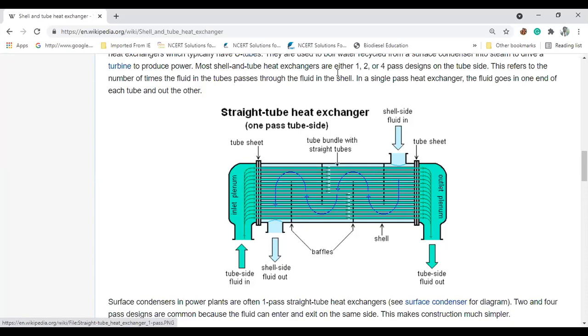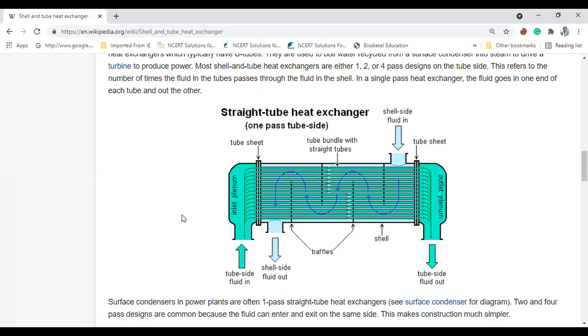Usually when you are dealing with a very high pressure fluid, try to keep that inside the tube. Please remember: high pressure fluid should always be kept on the tube side. On the shell side, you should keep a low-pressure fluid. If the tube ruptures or is damaged, everything will be constrained inside the shell — there is no damage to the outside world.